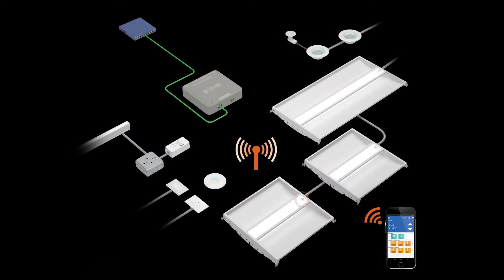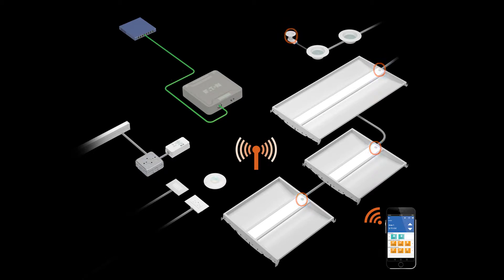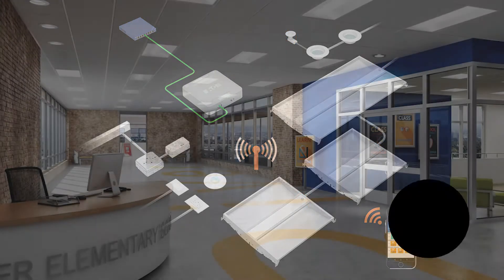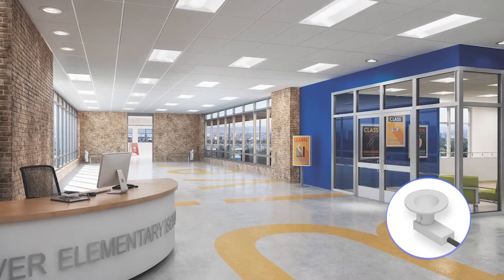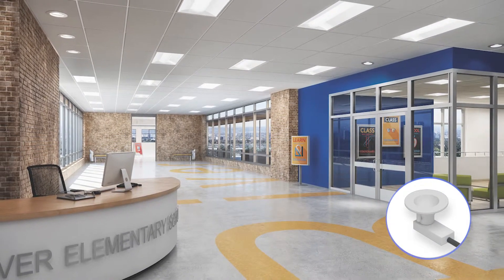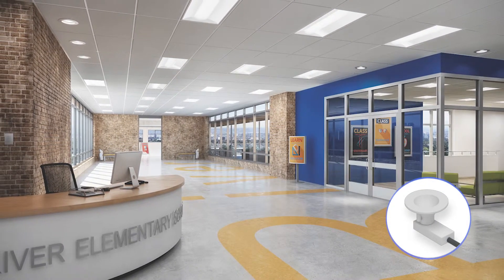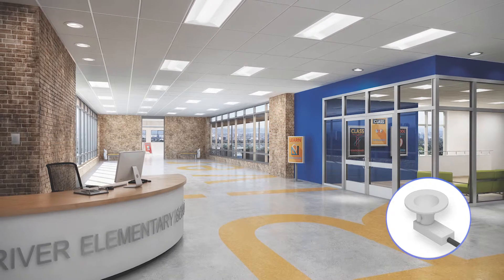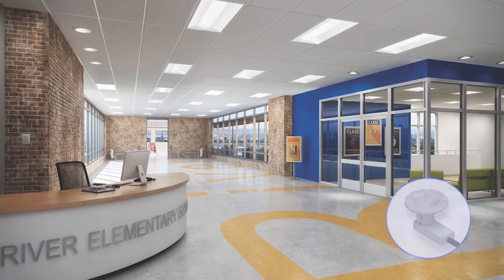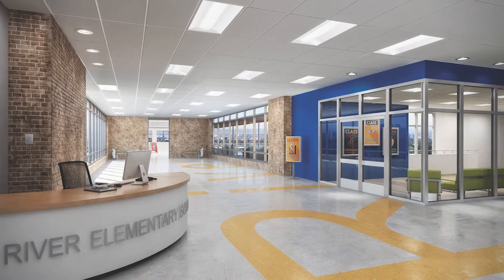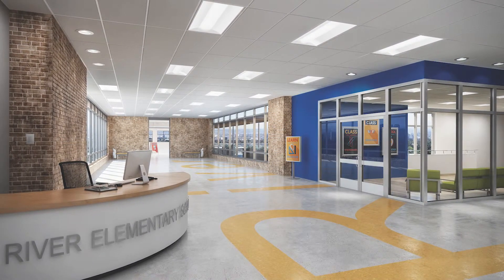Fixtures containing integrated sensors or connected to tile-mount sensors will automatically respond to available daylight. The sensor will reduce or increase the light level of the connected fixture to maintain a 500 lux target using closed-loop daylight control. All other commands will be scaled within the reduced daylight range to maximize energy savings.